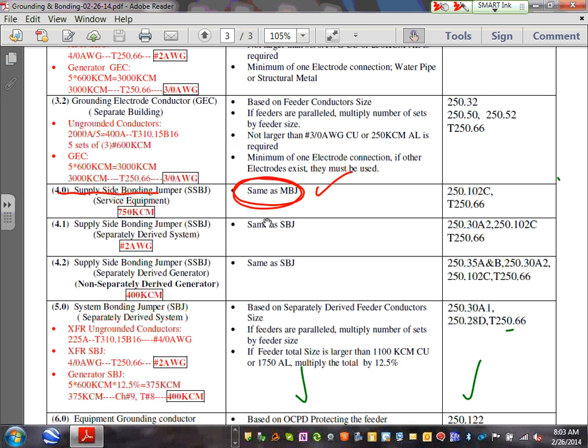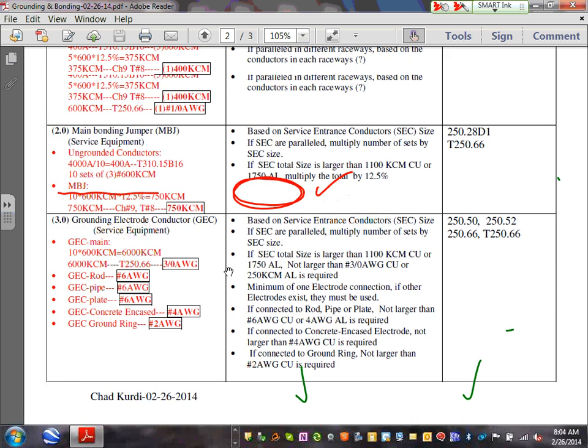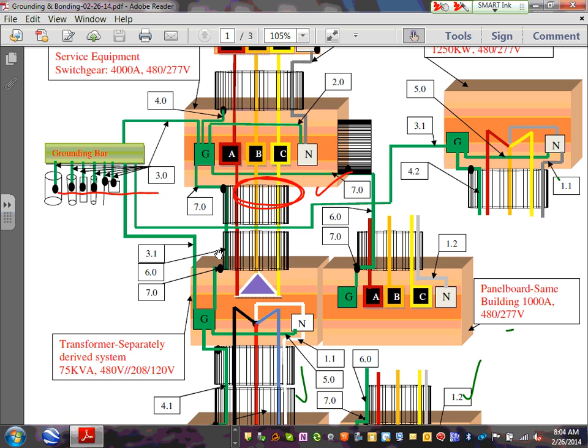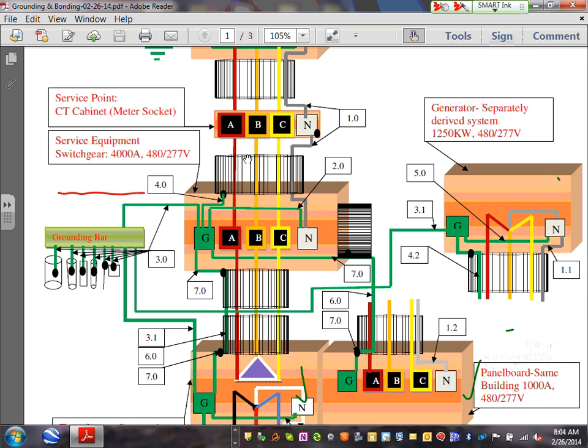Now, Karen, if my conduits are PVC, then the supply side bonding jumper shall not exist. Did you guys hear me? If it's PVC, you're not bonding PVC, are you? If it's EMT or rigid, anything metallic, you have to bond them. Okay, so that's my supply side bonding jumper, gentlemen. Can you guys see that? That's basically the grounding and bonding at the service. Any comments, guys? Any questions?